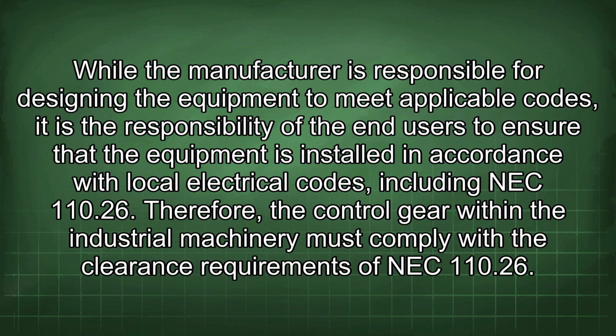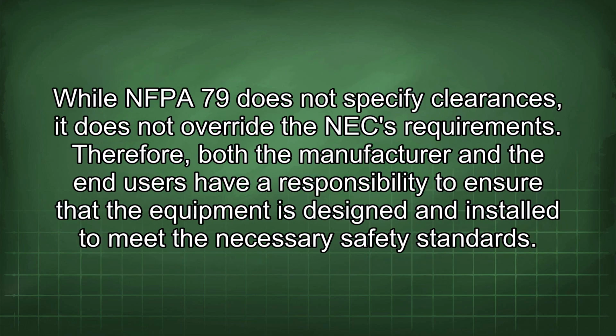While the manufacturer is responsible for designing the equipment to meet applicable codes, it is the responsibility of the end users to ensure that the equipment is installed in accordance with local electrical codes, including NEC 110.26. Therefore, the control gear within the industrial machinery must comply with the clearance requirements of NEC 110.26. While NFPA 79 does not specify clearances, it does not override the NEC requirements. Therefore, both the manufacturer and the end users have a responsibility to ensure that the equipment is designed and installed to meet the necessary safety standards.